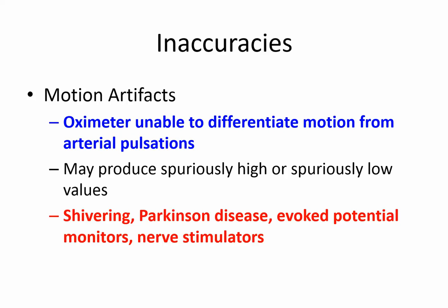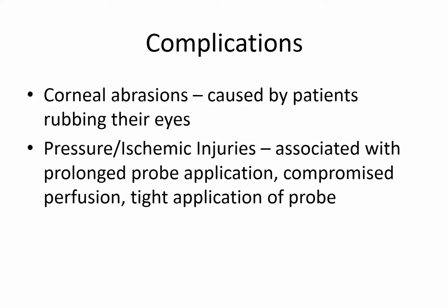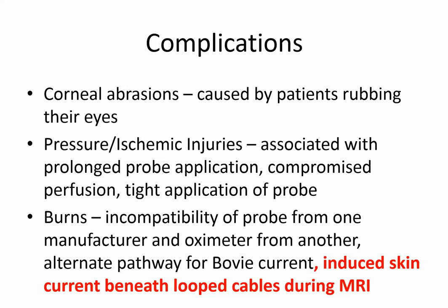Motion artifacts. The pulse oximeter can't differentiate motion from arterial pulsations, so it can produce either spuriously high or spuriously low values. There are some specific medical conditions or monitoring conditions that may produce this. You need to be aware of those. Complications. You know about the corneal abrasions because the patients rub their eyes. There are problems potentially with ischemic injuries because of too tight an application of the probe. The thing that's probably most important here is that if you use a pulse oximeter in the MRI and you loop the cables during the MRI, that in and of itself can cause a burn.